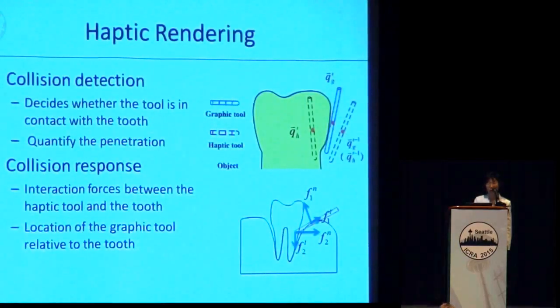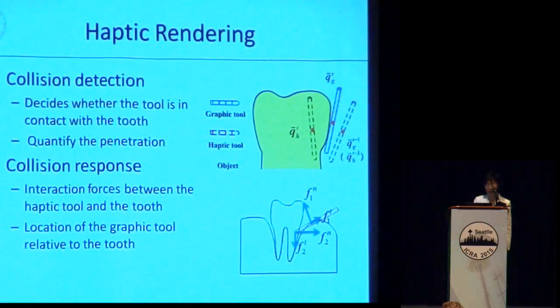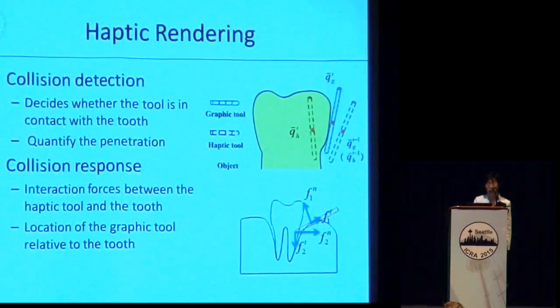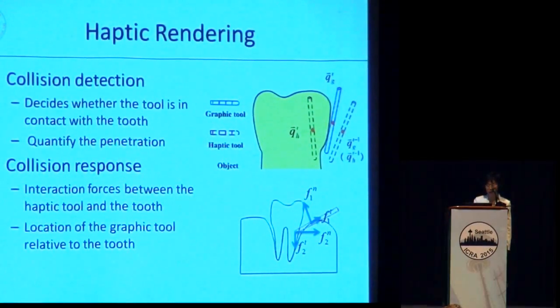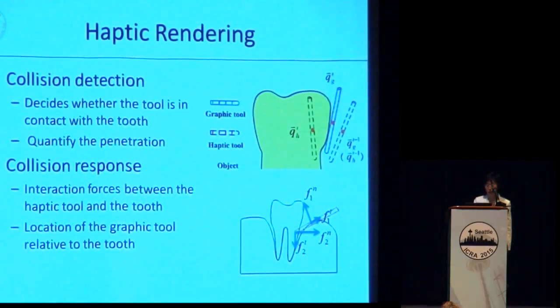The performance of a VR-based dental simulator relies heavily on haptic rendering. The process of haptic rendering involves two basic steps. The first is collision detection, in which the algorithm decides whether the tool is in contact with the tooth and, if so, how much the tool penetrates. The second step is collision response, in which the algorithm computes the interaction force between the haptic tool and the tooth, and determines the location of the graphic tool relative to the tooth.